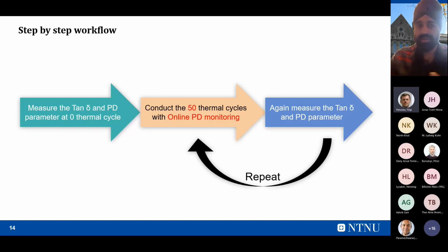Those tests are the tan delta test and partial discharge. I'll explain tan delta and partial discharge in detail in the next slide. So we measure the tan delta and partial discharge parameters at zero thermal cycle. After this, we conduct 50 thermal cycles with online partial discharge monitoring, that is, continuous partial discharge monitoring. Then we de-energize the entire setup, and again measure tan delta and partial discharge, and we keep on repeating this step. So we conduct 50 thermal cycles, and after this we go for measurement of tan delta and partial discharge values. So now, what is tan delta?